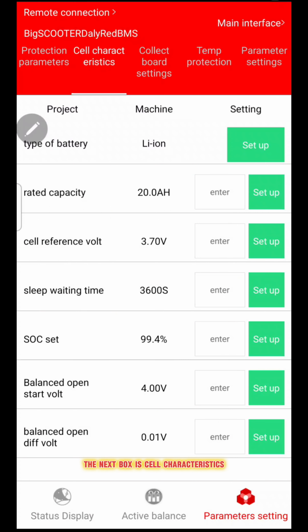The next box is cell characteristics. So you've got type of battery, and you can change this to LFP, LTO or lithium ion. Now I'm on lithium ion, so that's what we're set at. You enter your rated capacity of your pack, total capacity. Cell reference voltage, I've run that at 3.7, which is what's generally recognised as the reference voltage for a lithium ion 18650 battery. Sleep waiting time, this basically says after 3600 seconds the BMS will go into sleep mode, and it's woken up if you charge or discharge the battery. So if you power up your bike, the minute it powers up, it will switch the BMS back on.